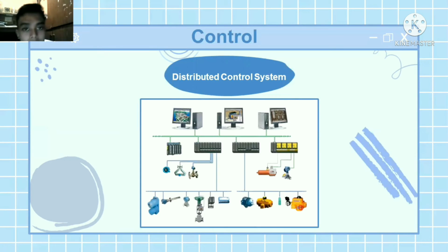DCS, or Distributed Control System, is a specially designed automatic control system that consists of geographically distributed control elements over the plant or control area. It differs from the centralized control system, where a single controller at a central location handles the control function. In DCS, each process element, machine, or group of machines is controlled by a dedicated controller. DCS consists of a large number of local controllers in various sections of the plant control area, connected via a high-speed communication network.